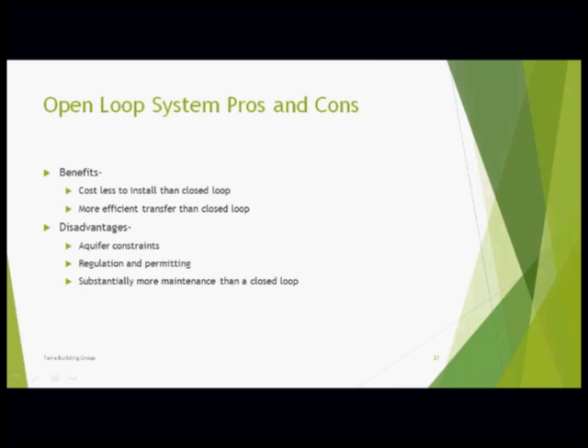Advantages and disadvantages of an open loop system: the advantage is they cost less than a closed loop, and they are more efficient in transferring the heating or cooling. Some disadvantages relate to your aquifer - sometimes the flow isn't high enough, sometimes it has too high of a mineral content, or you have sand or sediment that are issues that need to be filtered out. Some areas have a lot of regulation and permitting to overcome for an open loop, and there's more maintenance with your equipment - you're sucking in sediment and sand that needs filtering, and you have hard water issues.